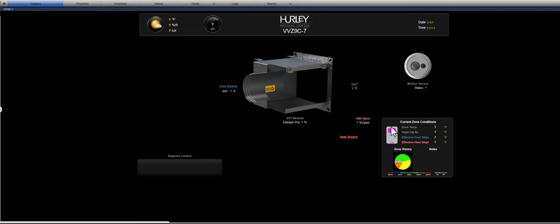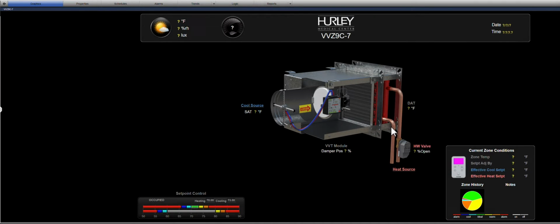Going back into the zone, we have to understand that this system was designed before computers. So the amount of electronic equipment in the nurse's station is going to add a significant load. One personal computer can add up to 1,000 BTUs per hour. One person is usually around 300 to 600 BTUs, so that's nearly two people's load, and there are probably the equivalent of 10 PCs or 10 pieces of electronic equipment kicking that out. So it has greater occupancy or heat load than when it was designed. We have to keep that in mind.